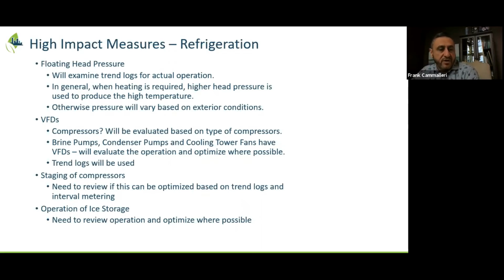So VFDs, again, we talked about it. We're looking into the viability of VFDs on compressors. And what we're seeing more and more commonly done is VFDs on brine pumps. We've seen that on condenser pumps as well as on cooling tower fans. And again, trend logs are going to be very helpful to help us understand the opportunity, the potential to save based on their current operation. And just because they have VFDs doesn't necessarily mean they're efficient today. We typically find opportunities for improvement on that. Again, trend logs are the key thing here to understand the existing facility. We'll also be focusing on how compressors are staged. Again, coming back to trend logs to understand how it currently operates, and trying to understand if there are improvements in the way you stage things depending on the loading that is occurring on the compressors themselves.